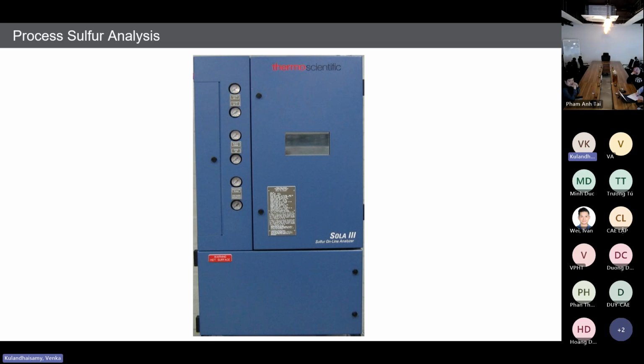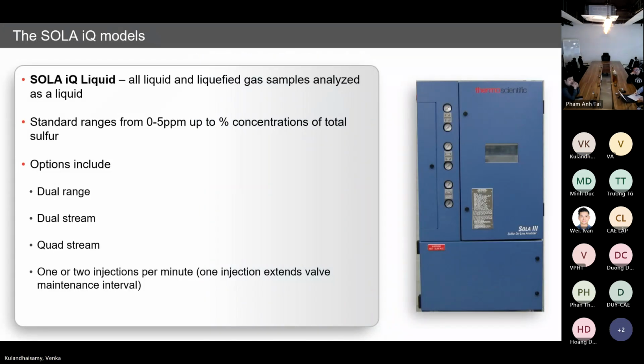You have already seen the overall view of our SOLA IQ analyzer. We have four different models of SOLA IQ analyzer, depending upon the application. First, the SOLA IQ liquid analyzer. All liquid and liquefied gas samples can be analyzed by this model. The standard range is 0 to 5 ppm, and up to percentage concentration levels can be measured.